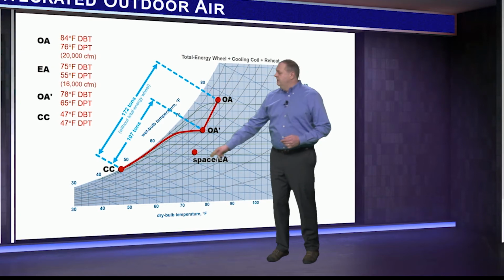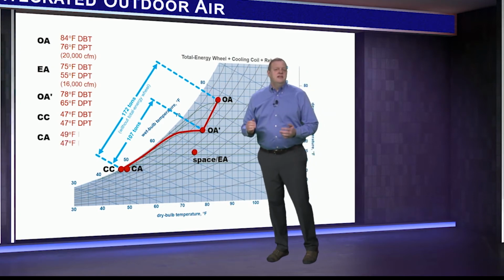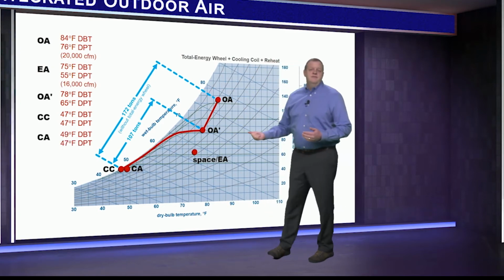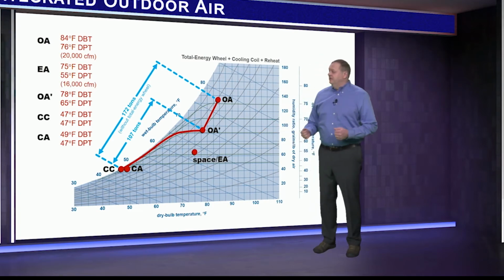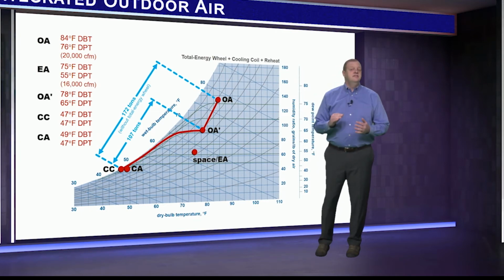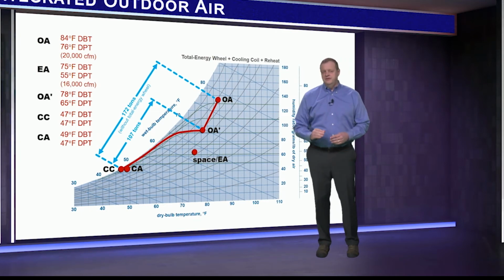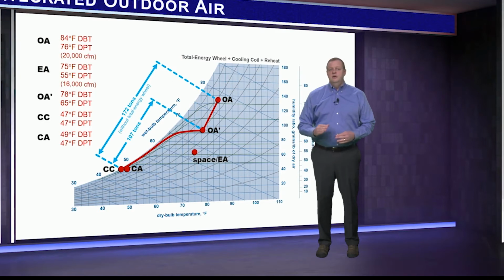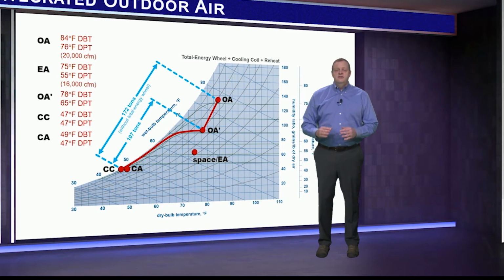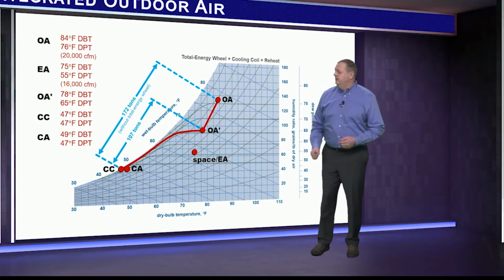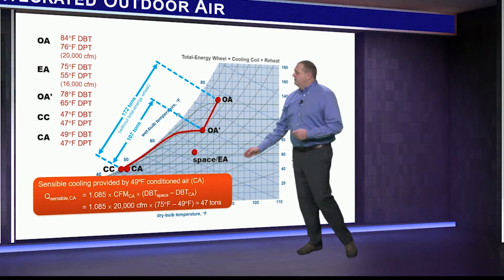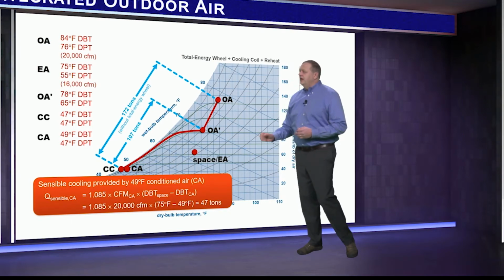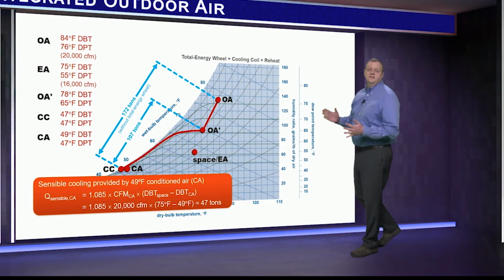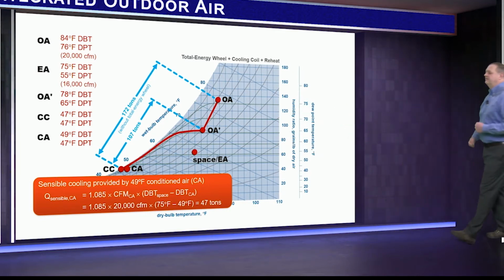Now for this example, with the exception of a few degrees of heat gain from the fan, I'm showing this dehumidified air not being reheated. So it's delivered down the duct at 49 degrees dry bulb. Now because this dehumidified outdoor air is colder than the zone temperature set point, it will offset part of the zone sensible cooling load. This allows the sensible coils in the terminal units to be smaller. At 49 degrees, 20,000 CFM of this cold air will offset a total of 47 tons of the sensible cooling load in the zone.